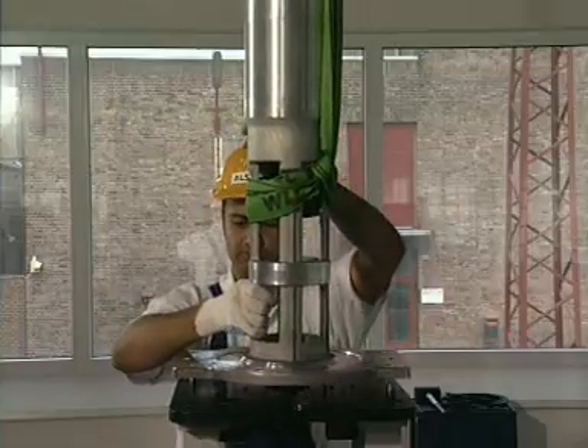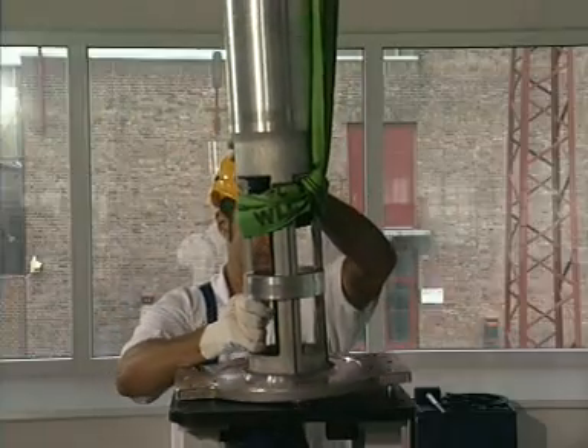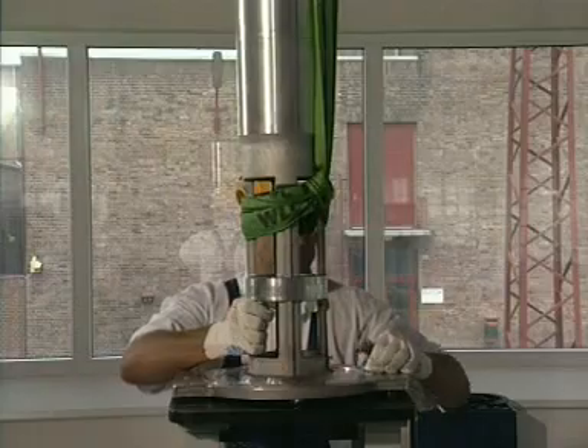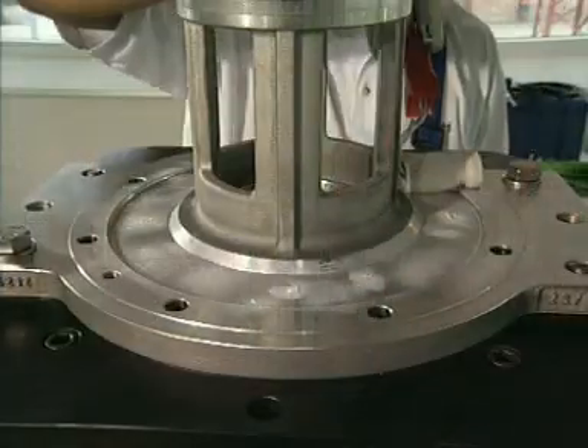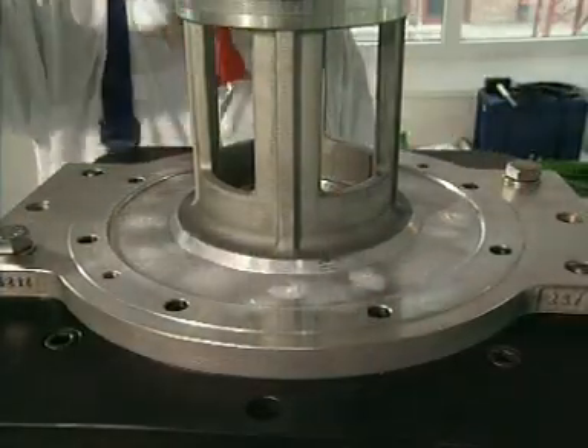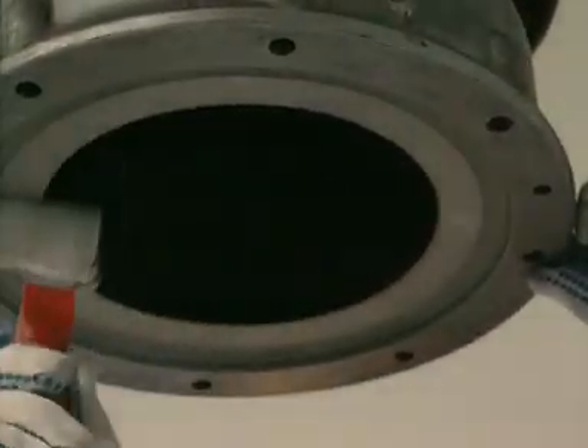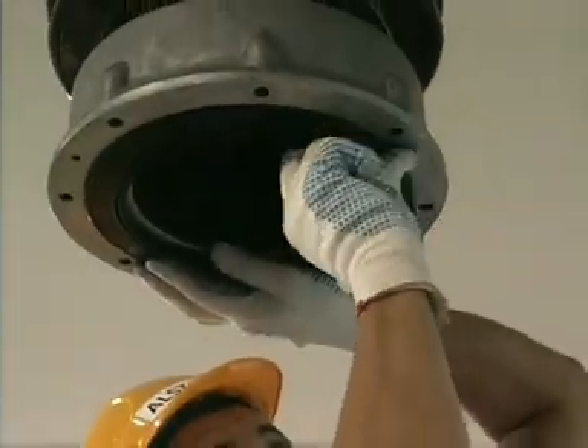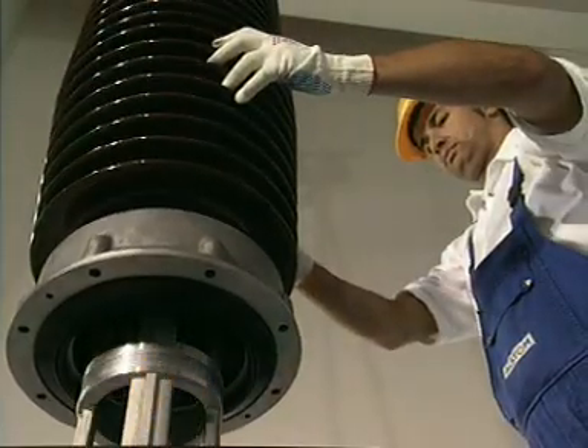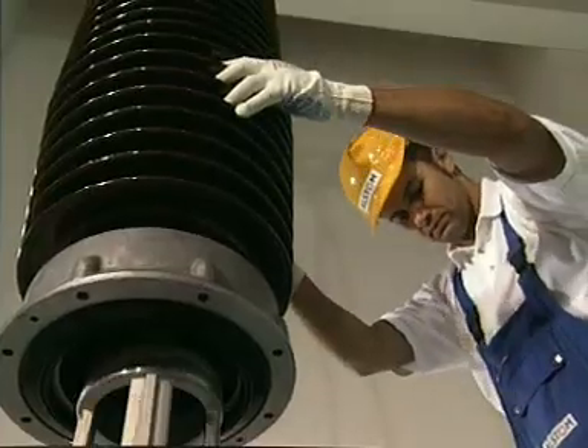Place a new contact carrier on the mounting fixture and secure it. Grease the sealing surfaces of the contact carrier, as well as the cleaned chamber porcelain, and position new gaskets on both flanges. Place the chamber porcelain on the contact carrier and tighten the bolts using a torque wrench.